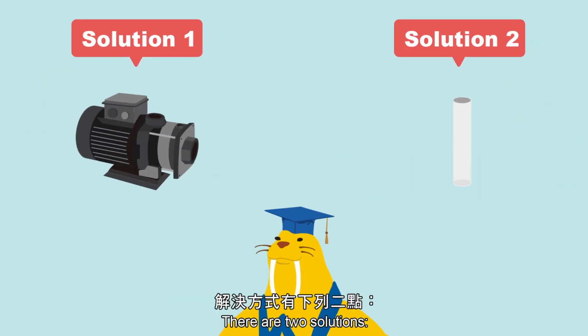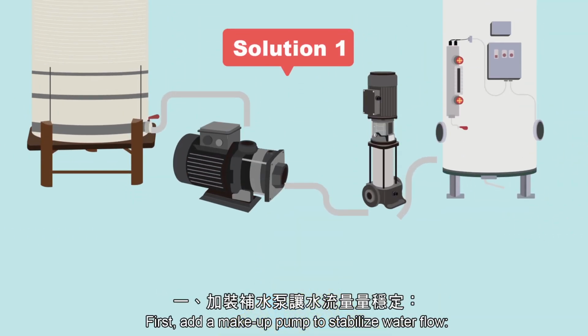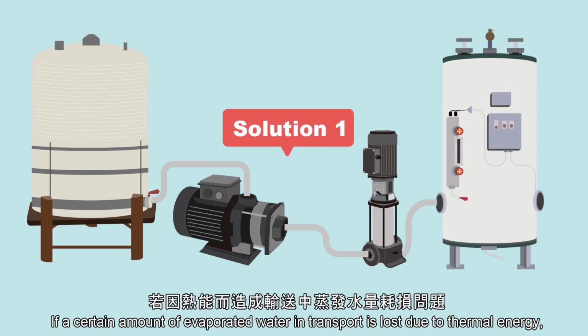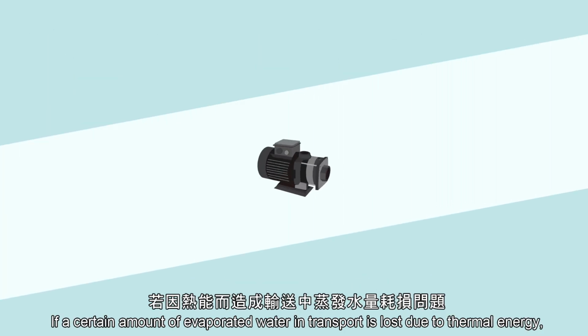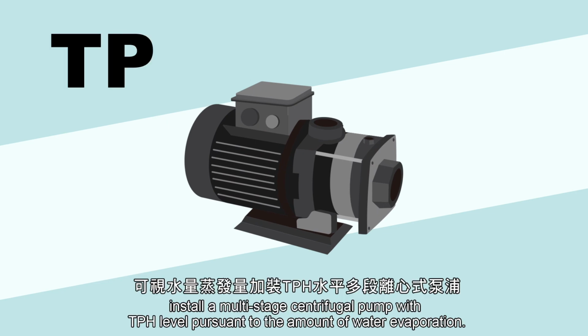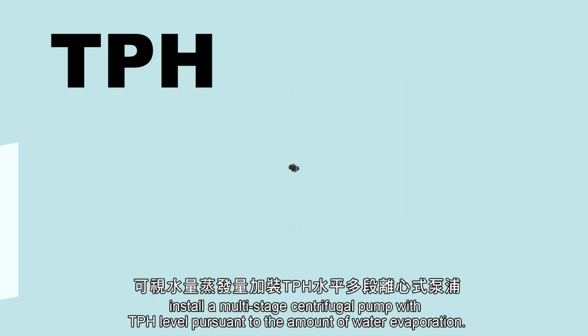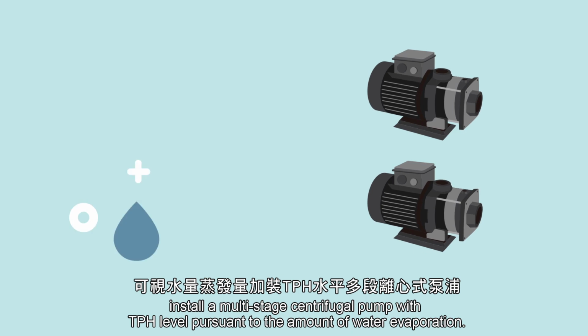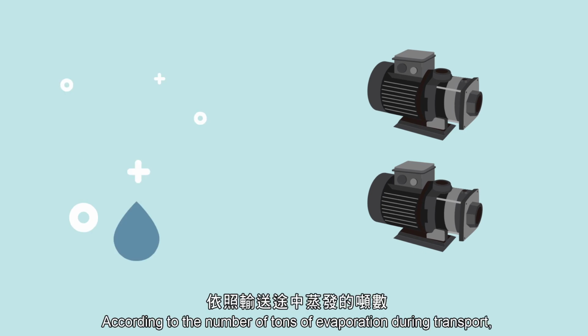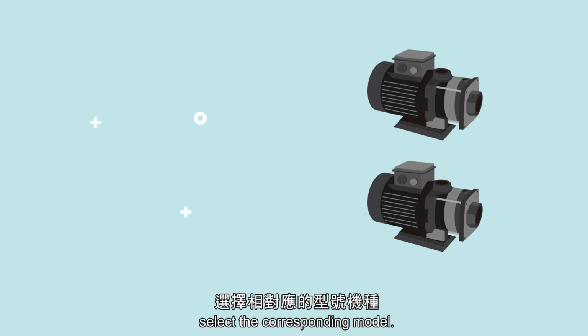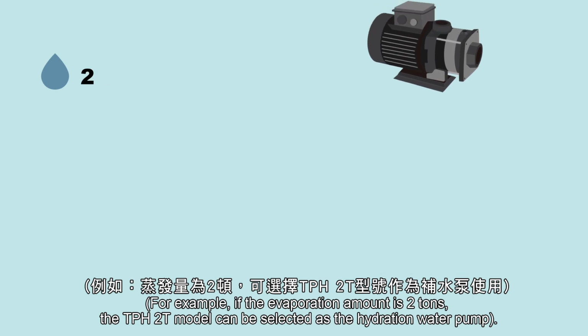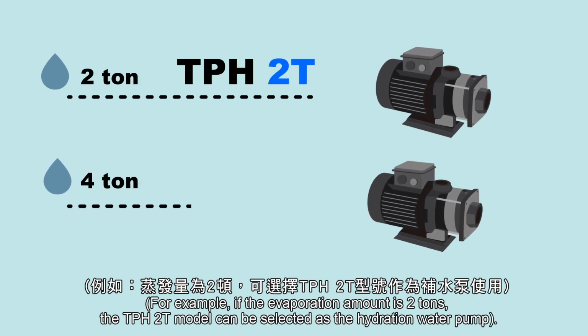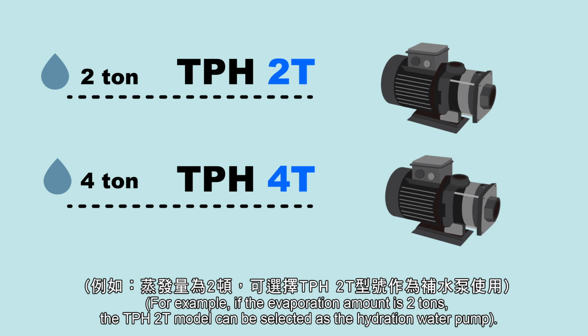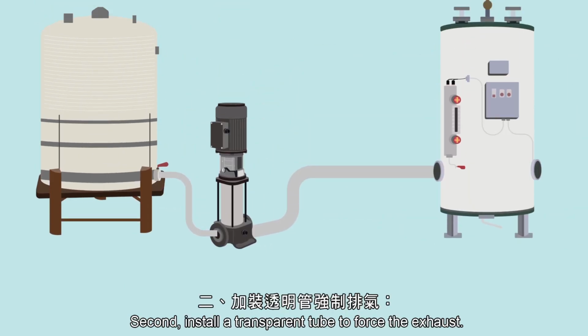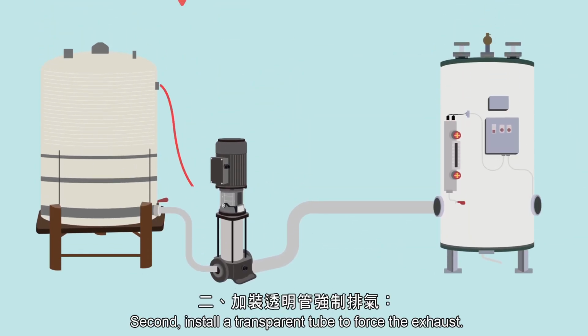There are two solutions. First, add a make-up pump to stabilize water flow. If a certain amount of evaporated water in transport is lost due to thermal energy, install a multi-stage centrifugal pump with TPH level pursuant to the amount of water evaporation. According to the number of tons of evaporation during transport, select the corresponding model. For example, if the evaporation amount is 2 tons, the TPH 2T model can be selected as the hydration water pump. Second, install a transparent tube to force the exhaust.